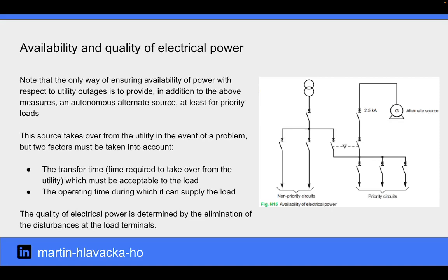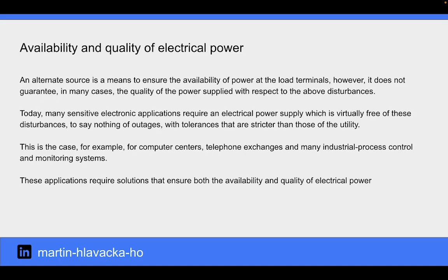Note that the only way of ensuring the availability of power concerning utility outages is to provide, in addition to the above measures, an autonomous alternate source, at least for priority loads. This source takes over from the utility in the event of a problem, but two factors must be taken into account: the transfer time must be acceptable to the load, and the operating time during which it can supply the load. The quality of electrical power is determined by the elimination of the disturbances at the load terminals. An alternate source serves to ensure the availability of power at the load terminals. However, it does not guarantee in many cases the quality of the power supply.